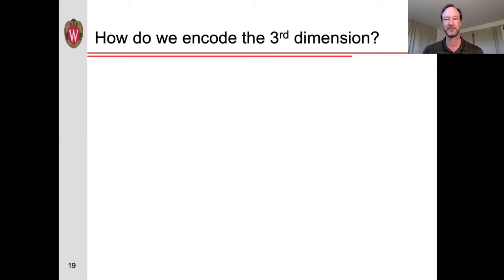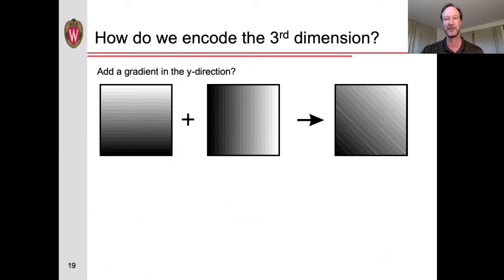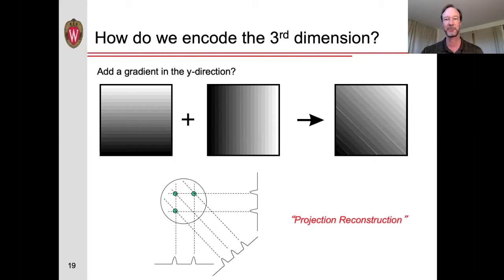So how do we encode the third dimension? If we apply two gradients at the same time, one in the x direction and one in the y direction, it just results in a new gradient in the x, y direction. So that just allows us to see where the signal is coming from along that axis. However, if we repeat this process multiple times and each time varying the x and y gradients, we can use these set of signals, each of which is essentially a projection of the image perpendicular to that axis to reconstruct the image, a technique that's called projection reconstruction.